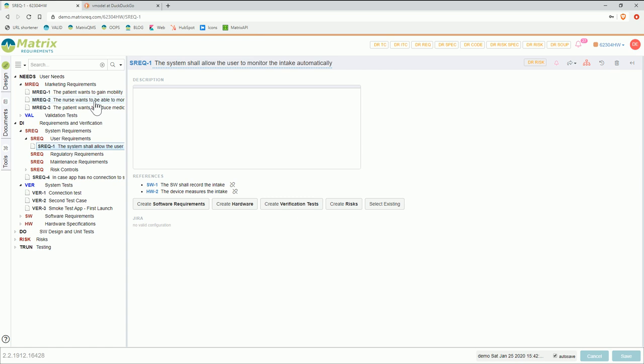Of course what you need is all the requirements which make your device unique and all the requirements which tell people what your device can do — basically whatever you write in your intended use on your marketing package. Also, if your device grows and you make a second and third release and you figure out that people ask a lot about certain features, over time you can add them to your marketing requirements. But for a first release keep it simple — 10 to 20 might be enough.